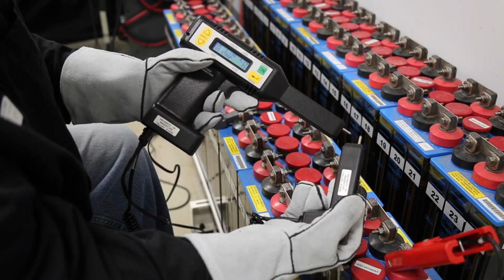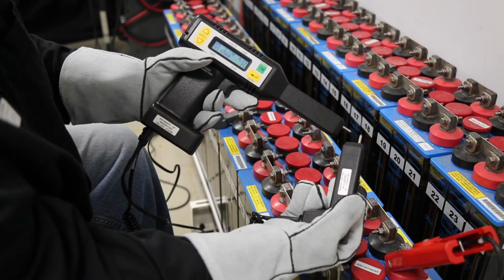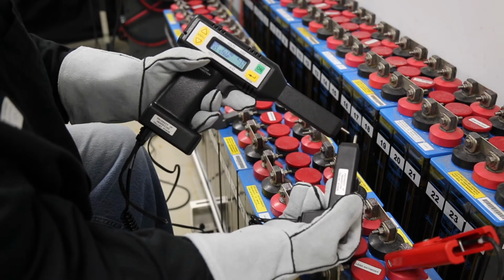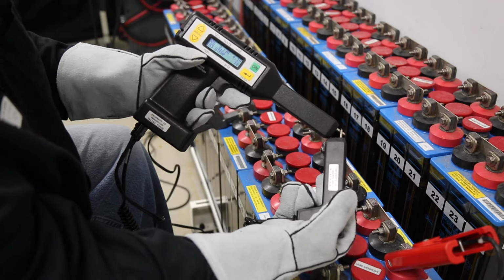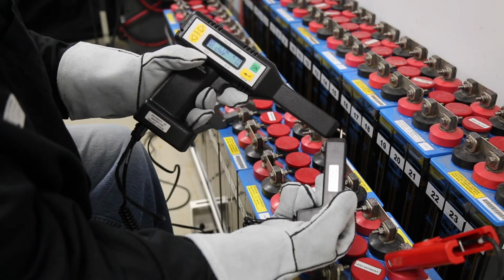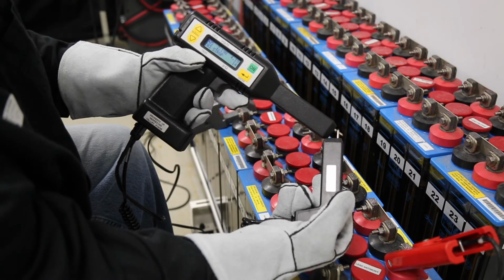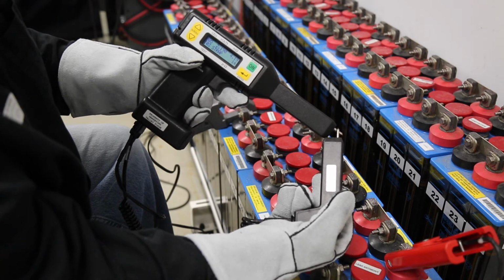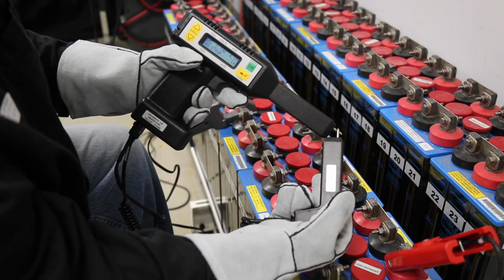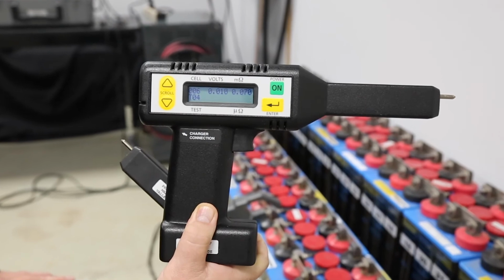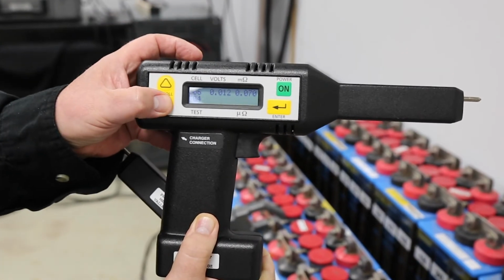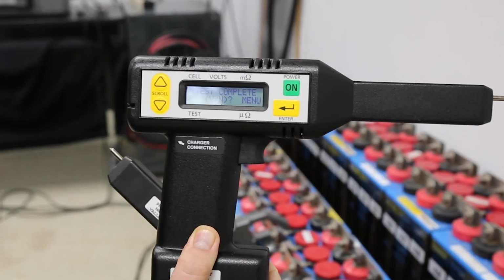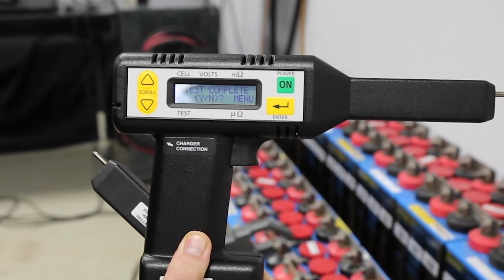The BITE2 saves these values in cell strap combinations. So when we reach the last cell, we need to take a dummy strap measurement. Simply touch the probes together and then pull the trigger to save the measurement. We're now done with the testing. So we just measured the last battery in our string, and now we want to look at the recorded string data. So we push the down button.